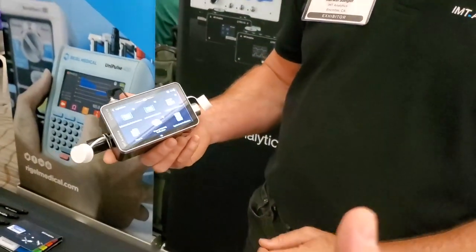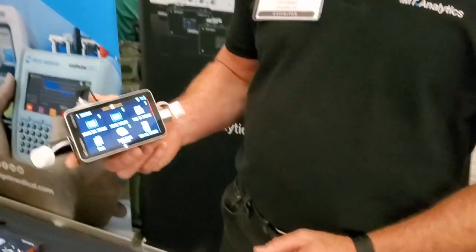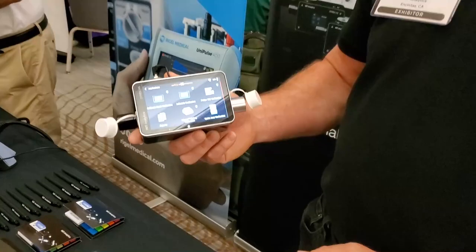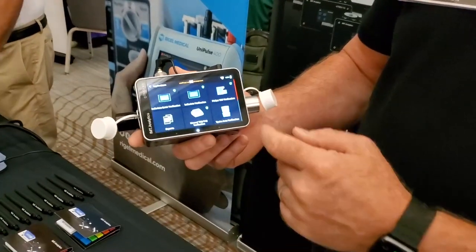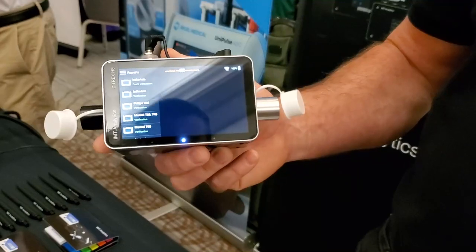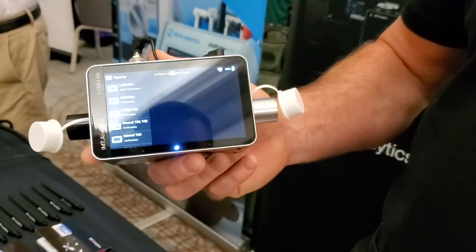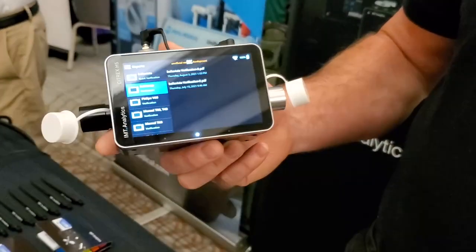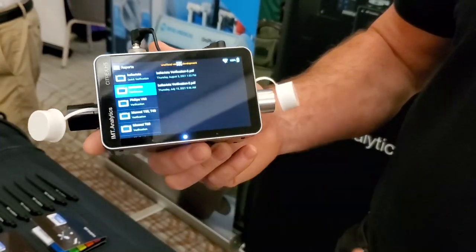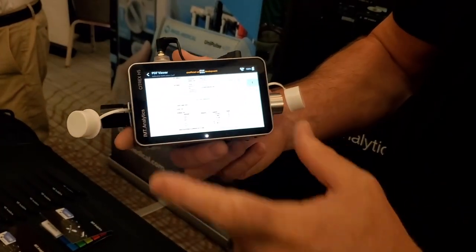The device I had was a demo, so they just set up different profiles — that's what I was used to seeing. Also on this screen, you'll see that all your reports are here. Anytime you create a report using one of the apps, it separates it by the ventilator type, and you can see the reports there and view them on the device if you want to. You can zoom in on them.